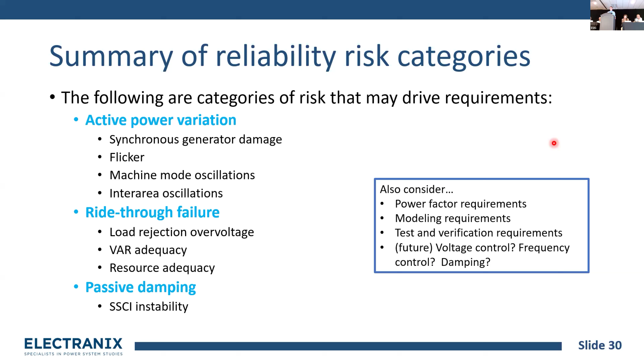There are different philosophies for writing or implementing these requirements. First, you could make this an individual requirement - every load comes in and is allowed up to a certain limit based on a study. You do an impact study for a load, considering the system around you, the synchronous generators, load profiles, voltage profiles, everything.